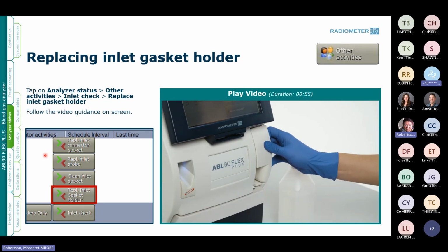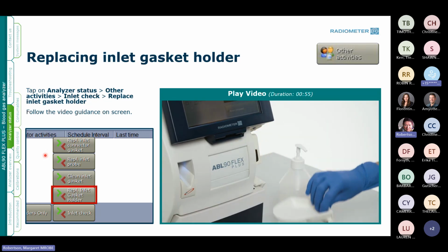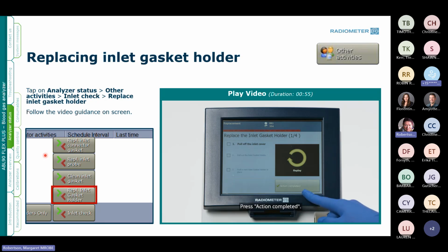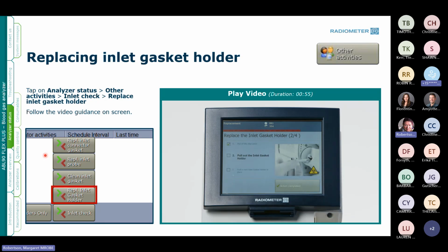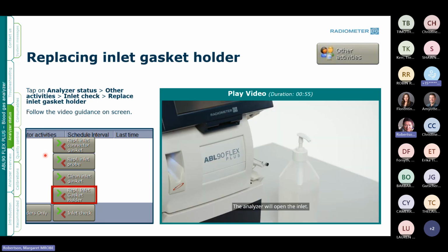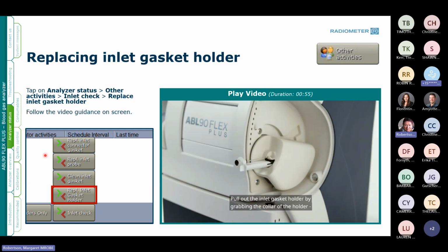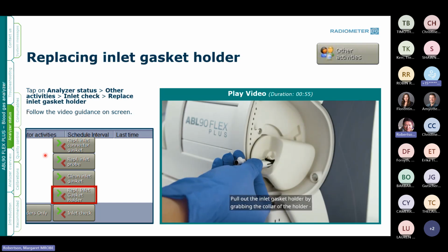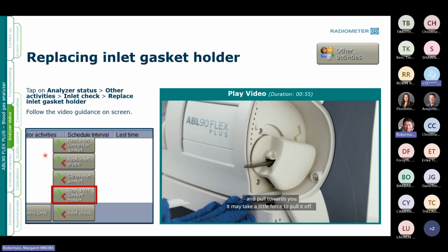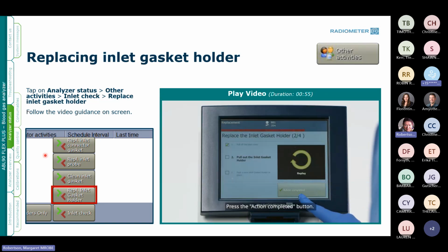Remove the inlet cover. Press Action Completed. The analyzer will open the inlet. Pull out the inlet gasket holder by grabbing the collar of the holder and pull towards you. It may take a little force to pull it off. Press the Action Completed button.